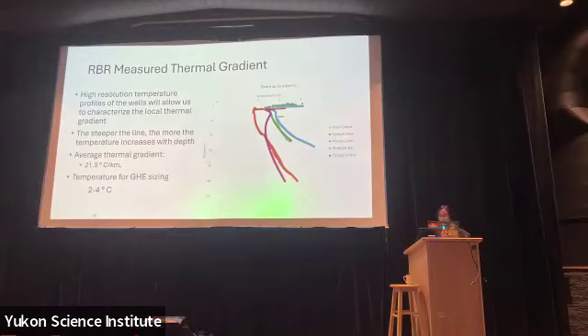Within these 5 wells that I've measured, the average thermal gradient was 21.9 degrees Celsius per kilometer. The measured average for Whitehorse in deeper wells, going to 500 meters depth, is actually between 26 and 28 degrees Celsius per kilometer, so that line is increasing the deeper you get. And we're using a temperature between 2 and 4 degrees Celsius for the ground temperature parameter that goes into the sizing of the ground heat exchangers.